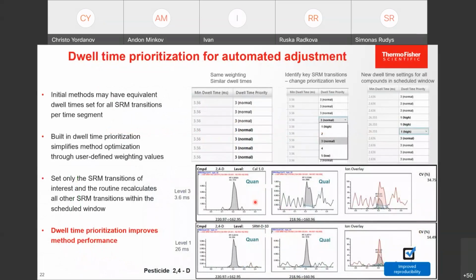Next thing on the TSQ Plus instruments is the dwell time prioritization and automated adjustments. So at the beginning, we set the peak width and we set how many cycles, how many transitions we want to collect per this peak, and it sets dwell time per each compound. So at this point, all transitions are equal. So we can see that for different compounds, we have the same dwell time.